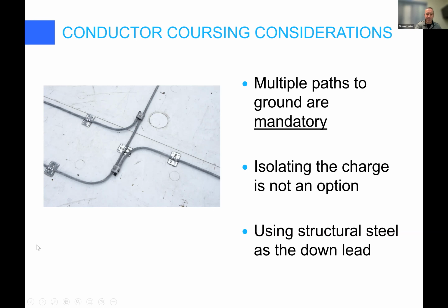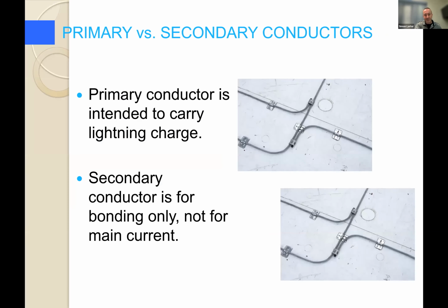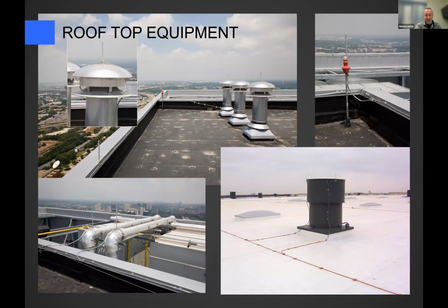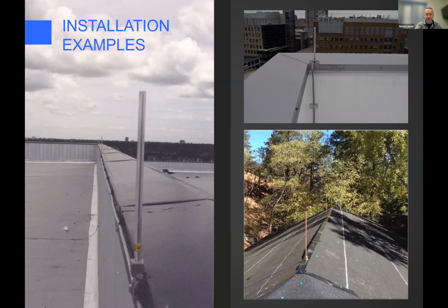Multiple paths to ground are mandatory. We are required to have 2 paths to ground for each lightning rod. So you can imagine those lightning rods there. The cabling goes straight through that base. It's got a path to the right. It's got a path to the left. You've got your 2 paths to ground.